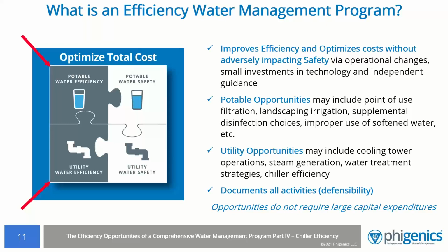Now, let's turn to improving efficiency and reducing costs. An efficiency water management program should focus on operational changes that result in immediate cost savings without jeopardizing performance, your capital assets, or water safety. We're not talking about large capital expenditures that have 10 to 20-year return on investment timeframes. In most facilities, the biggest opportunities lie in the utility water systems. But that is no longer always the case as building owners dedicate more and more resources to operating their potable water systems safely. An independent evaluation of your expenditures in both areas can turn up significant opportunities to conserve resources.